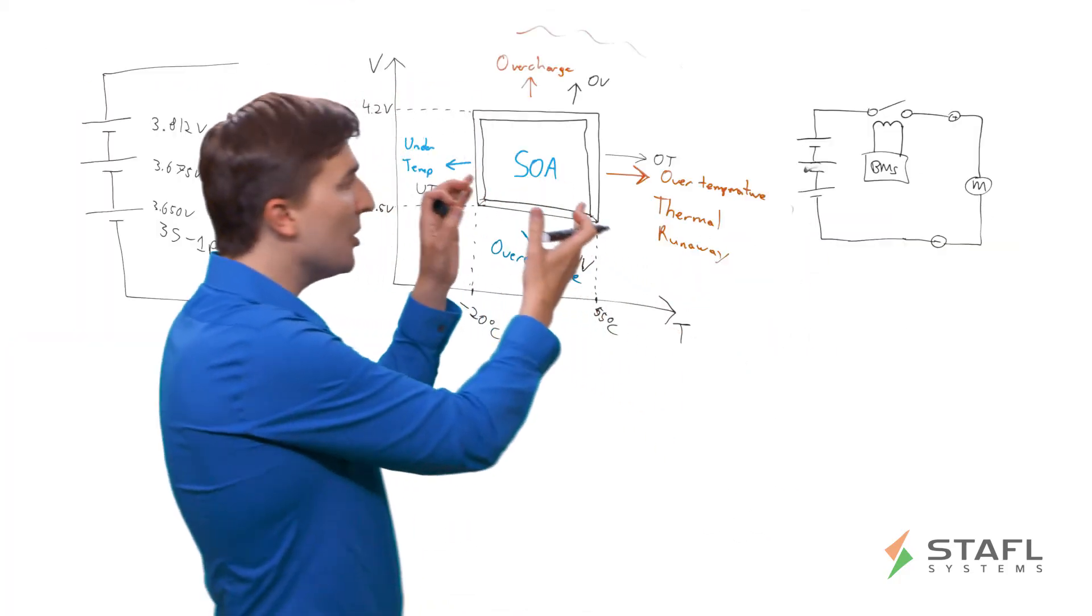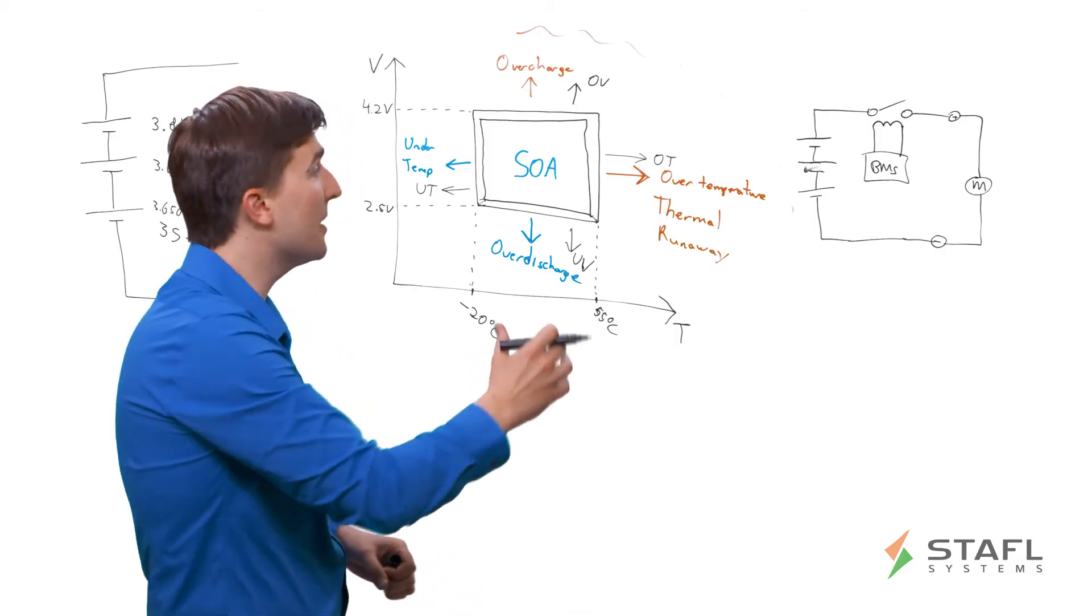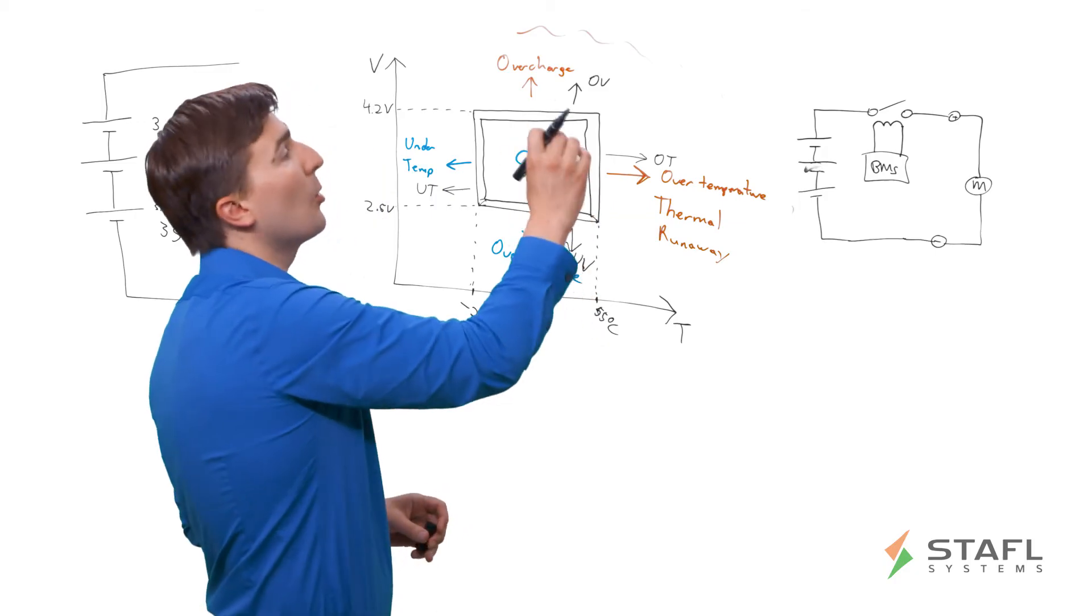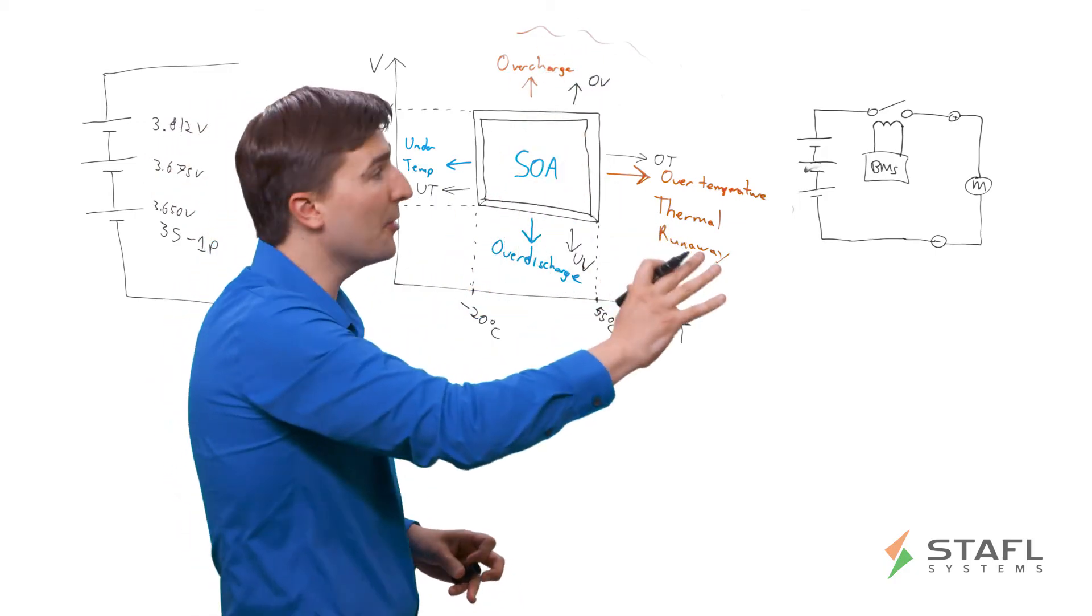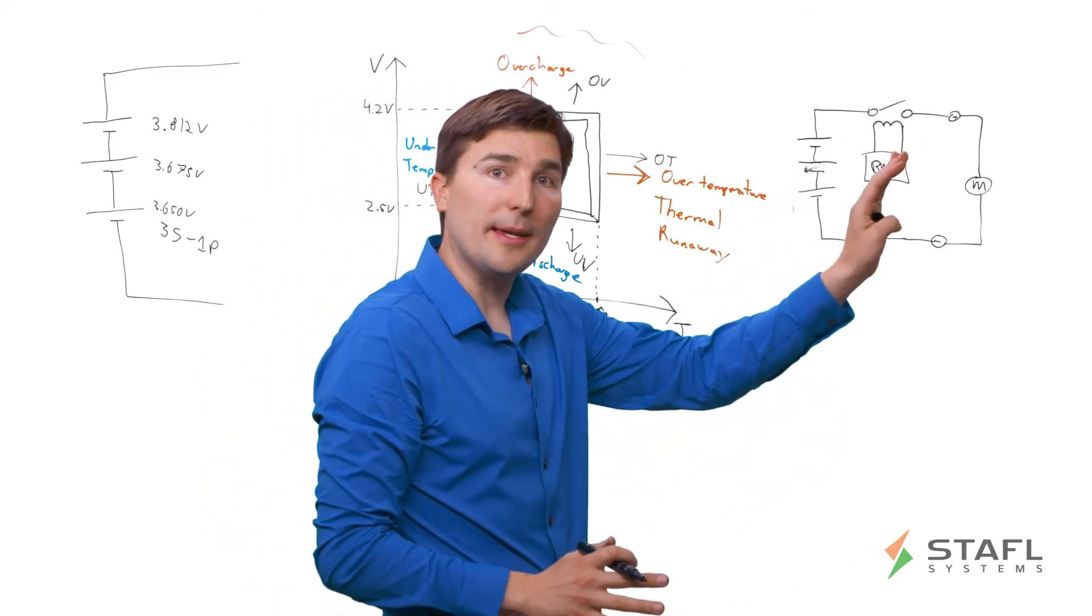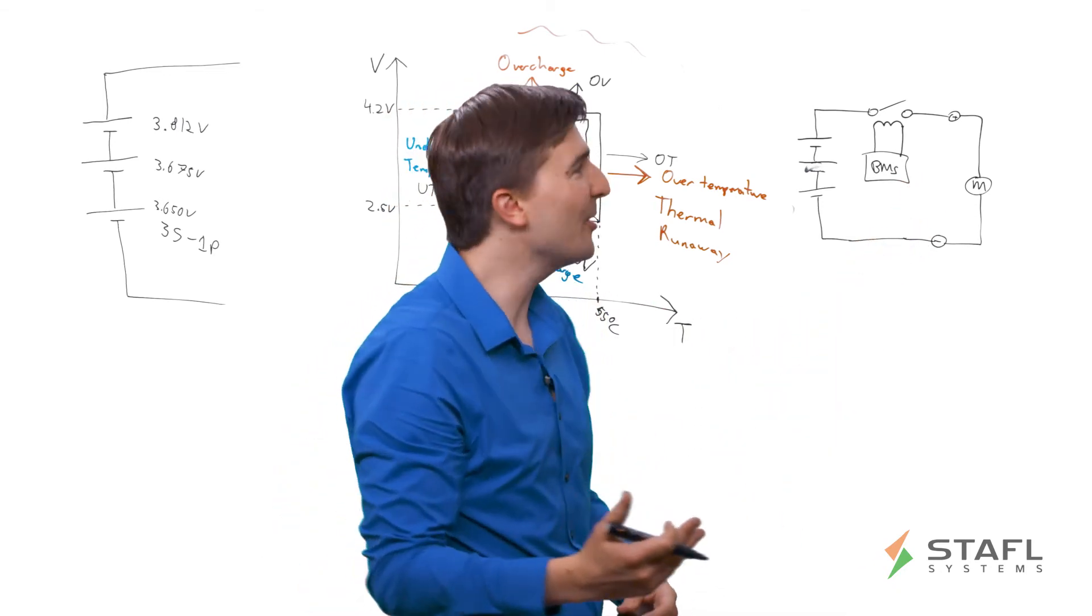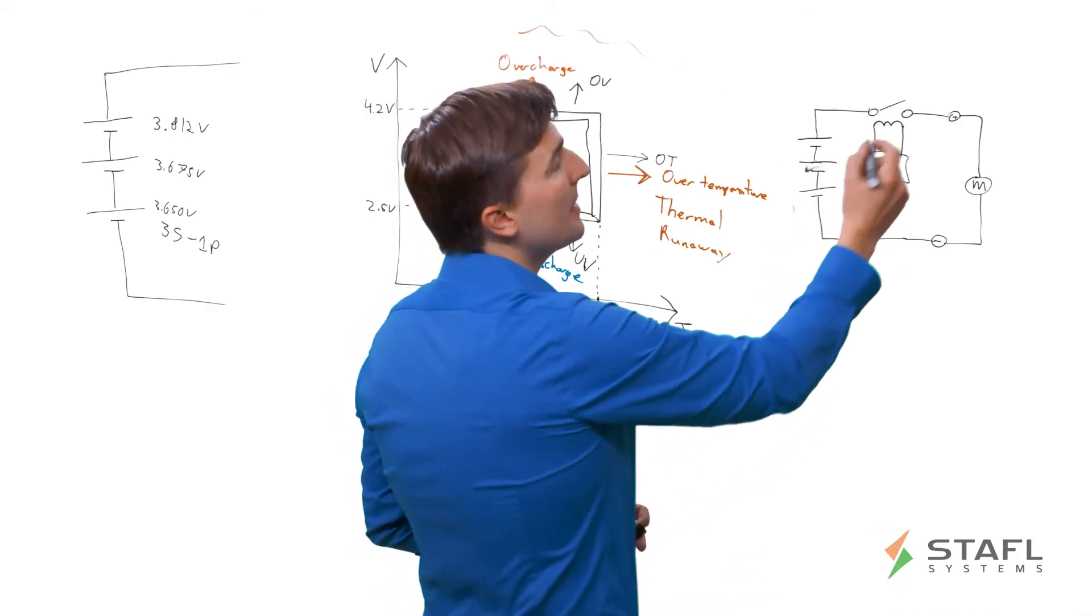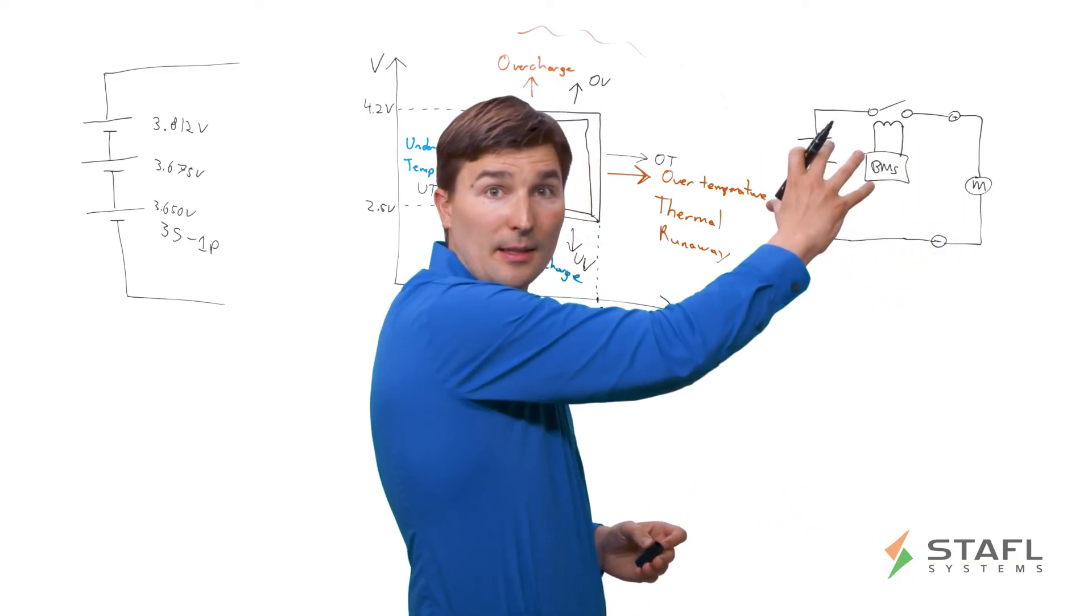So, for example, typically you will have a BMS that will communicate via its communication interface to the external system saying, one of the cells is getting too hot, or one or more of the cells is getting too overcharged. Do not charge me any further. It is the responsibility of the system controller to obey the BMS limit. Now, if it does not do that, and for example, it's malfunctioning, it's broken, the software is written incorrectly, then you have a situation where the BMS independently needs to be able to disconnect itself from the load or from the charger and protect the pack.